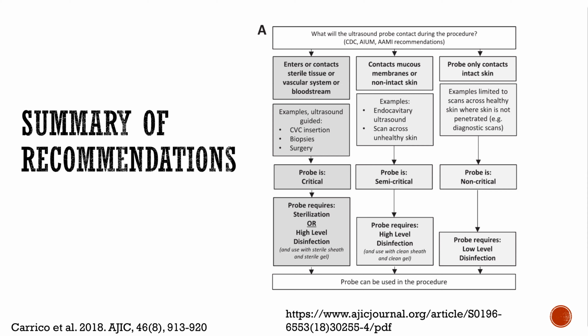So it really reinforces that if something is having contact with sterile tissue or the bloodstream, then it should be sterilized or at least high level disinfected. And then if it's considered to be semi-critical, again, high level disinfection. And if it's only having contact with intact skin, then low level disinfection is an appropriate option.